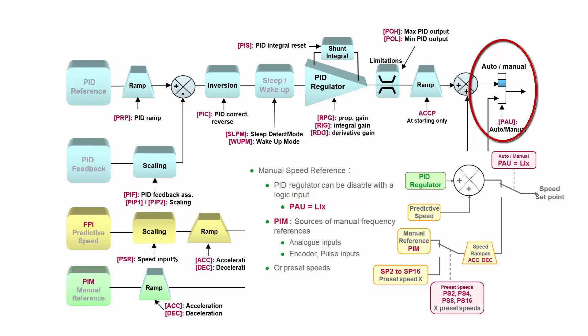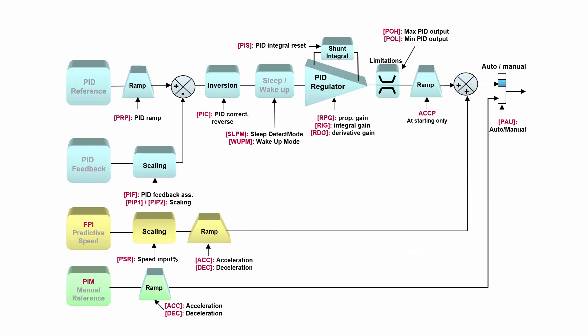Additionally, what we can do is supervise certain things inside PID regulator using SoMove software or HMI on the drive. So we can supervise feedback, we can set certain limits of error or warning, and then we can supervise all other values inside PID like error correction, output, reference, and so on.